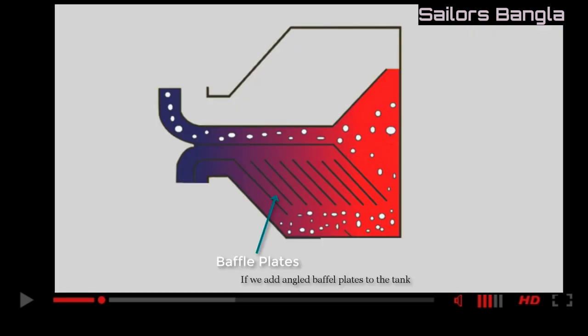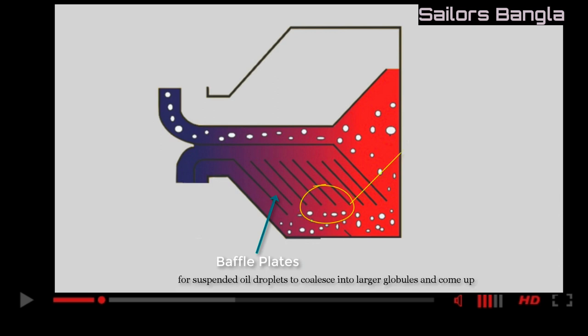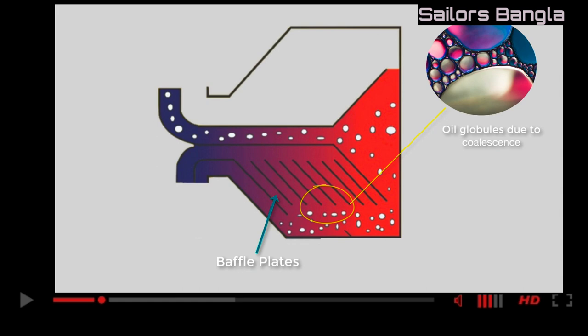If we add angled baffle plates to the tank, the underside of each parallel plate provides more surface for suspended oil droplets to combine into larger globules and come up. The solid particles will also slide down the surface of each parallel plate. This allows the denser liquid and solids to settle at the bottom, while the lighter fluid will rise up to separation.